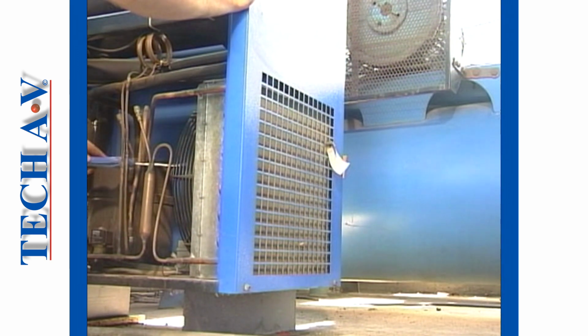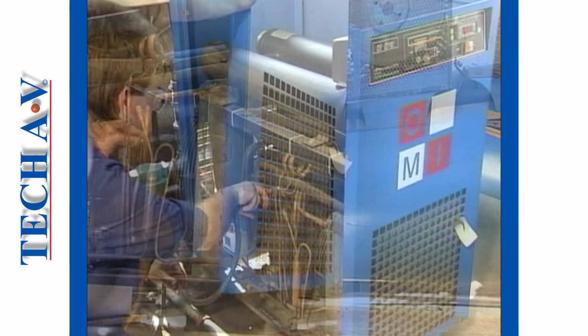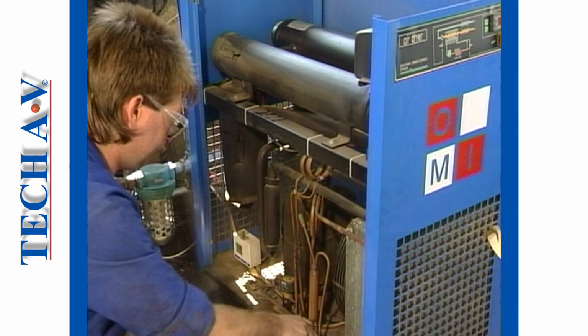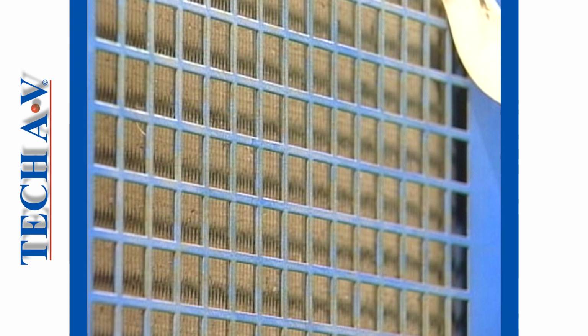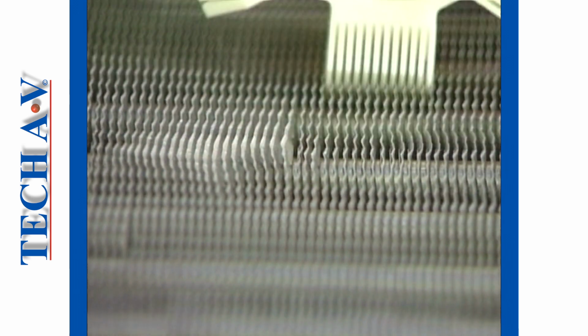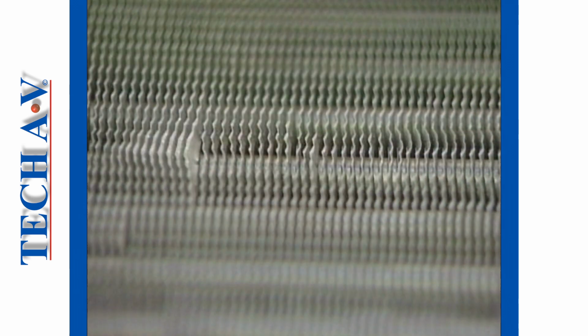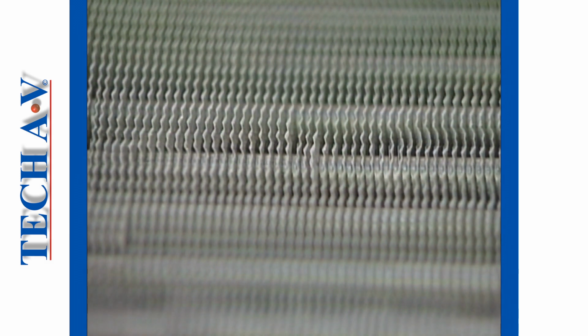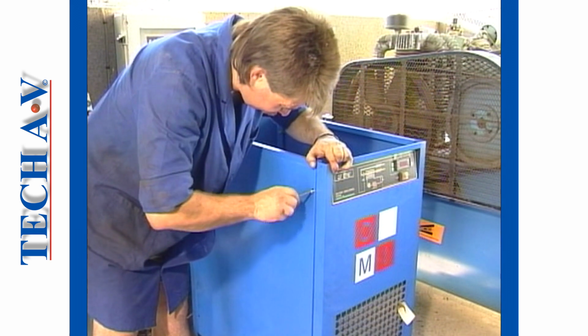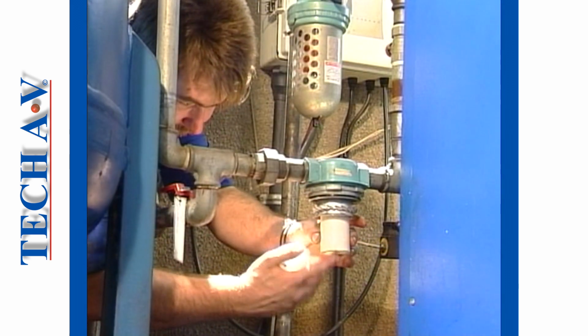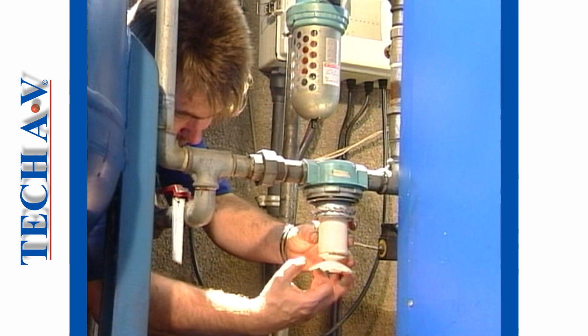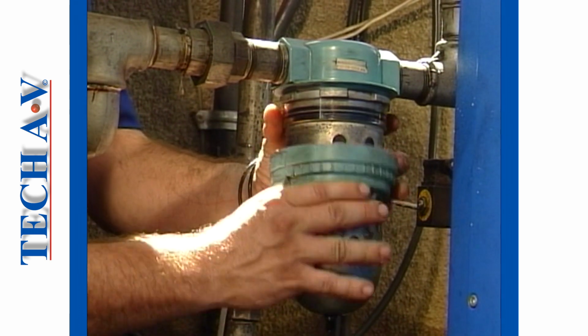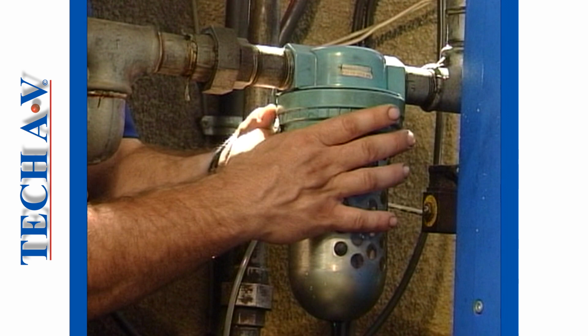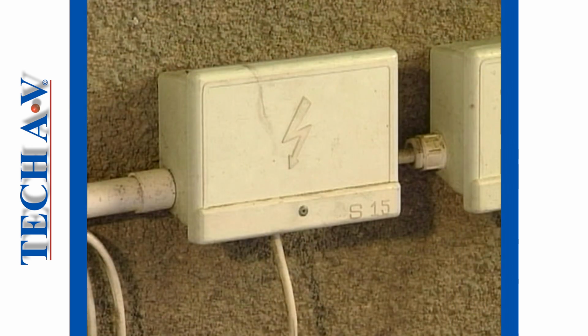Using compressed air, blow the dust and dirt away from the heat exchanger and the surrounding components within the cabinet. Carefully inspect the cooling fins of the heat exchanger. If you find any bent fins, then you will need to straighten them using a fin comb. Bent fins will result in a restricted airflow and poor condensing or drying of the air. Replace and secure the covers after you have finished cleaning inside. The separators connected to aftercoolers and dryers should be cleaned out at the same time that the unit is being serviced. Remember to reconnect the power supply where applicable.